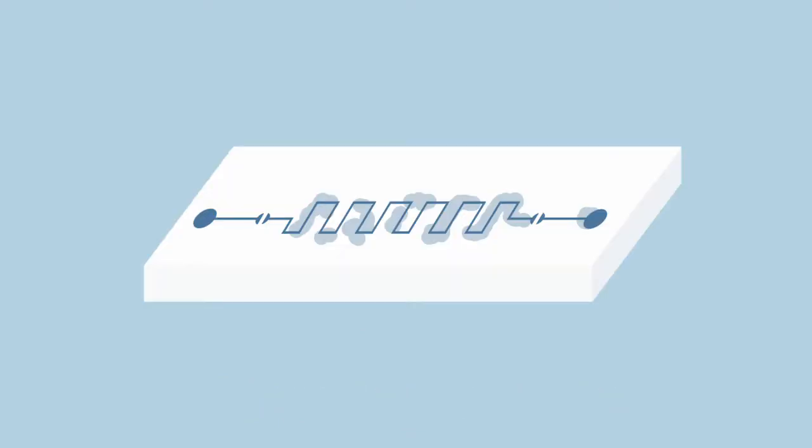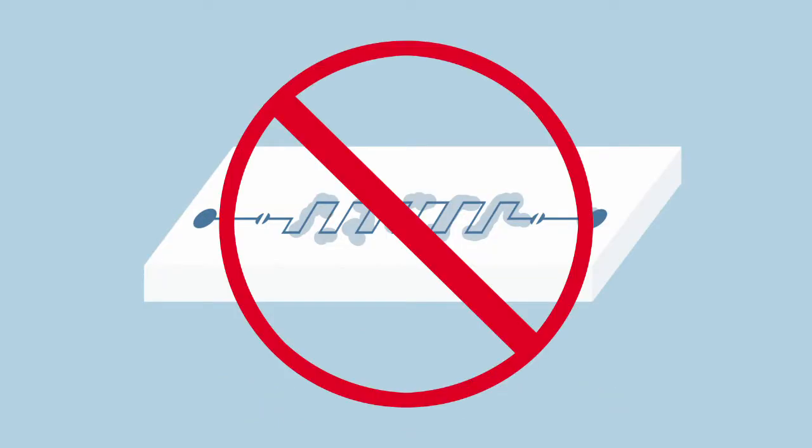It is extremely important to correctly clean and store chips as dust particles and any chemical residue will affect subsequent tests run on it.